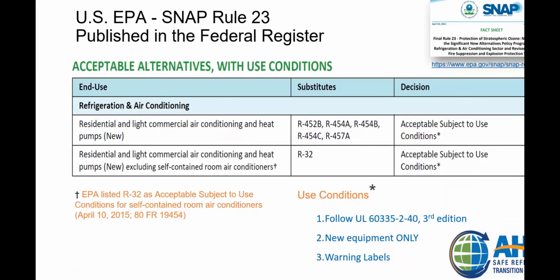410A in the dust. We're going to new refrigerants. The EPA has this thing called the SNAP rule. The SNAP rule defines all of the various refrigerants that can be used for various types of applications. The six refrigerants you see on the screen right now are the ones that the EPA has approved for use with residential and small commercial equipment that has scroll and rotary compression in it. There are different refrigerants that you can use for centrifugal chillers and screw chillers and stuff like that. But for your normal everyday stuff, this is what we've got to work with. All six of these refrigerants are flammable. So no matter what, people are getting a flammable refrigerant. And unfortunately, there's multiple solutions to one problem here.